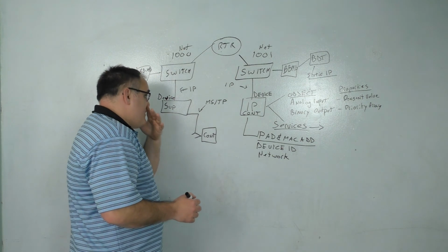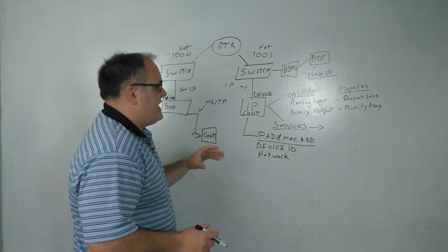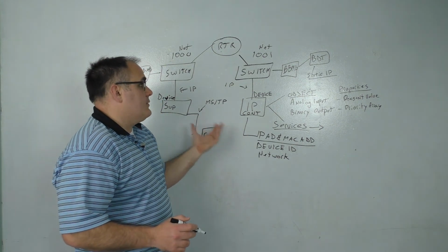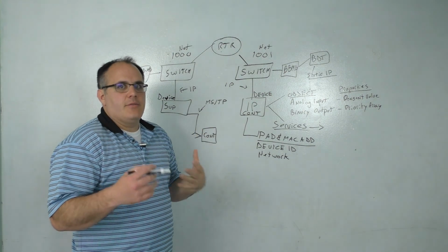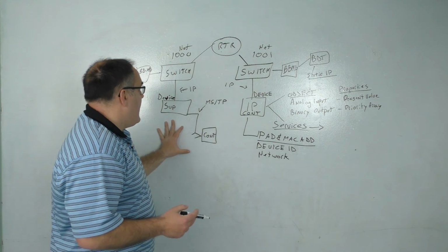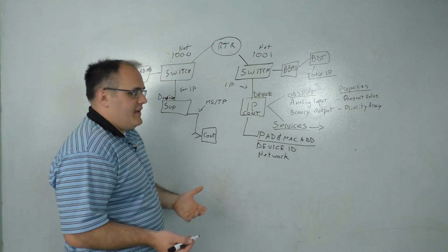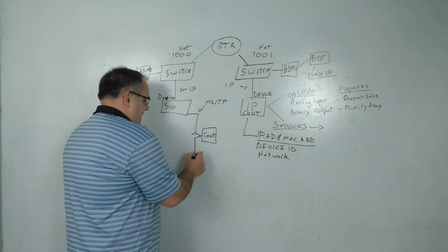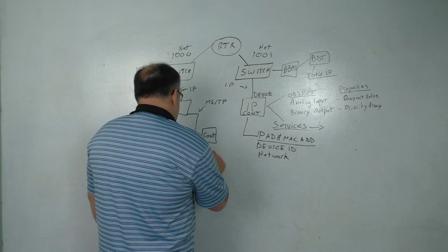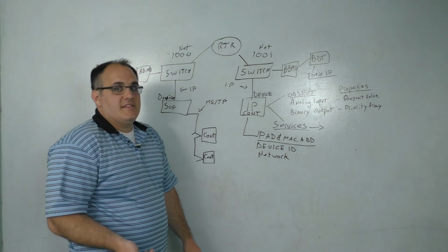Then on the other side, we have master-slave token passing. IP wasn't adopted heavily at first, except at the supervisory layer with BACnet, because it was viewed as more expensive back when BACnet was first created. Nowadays, we all know IP is pretty cheap. But BACnet MSTP was very cheap back then. It was a self-healing network. You could have, depending on who you talk to, anywhere from 32 to 64 devices on a segment.